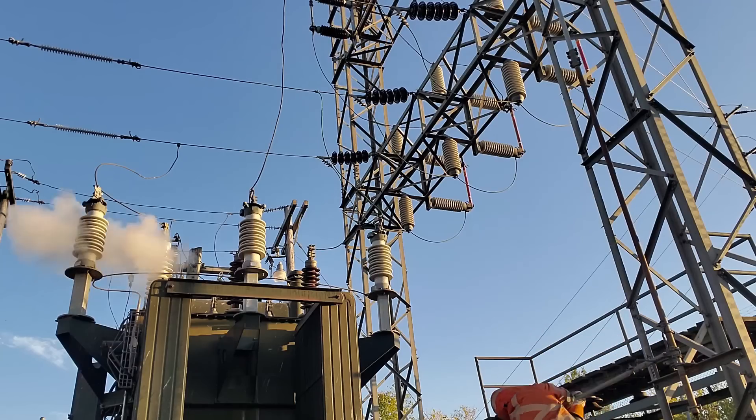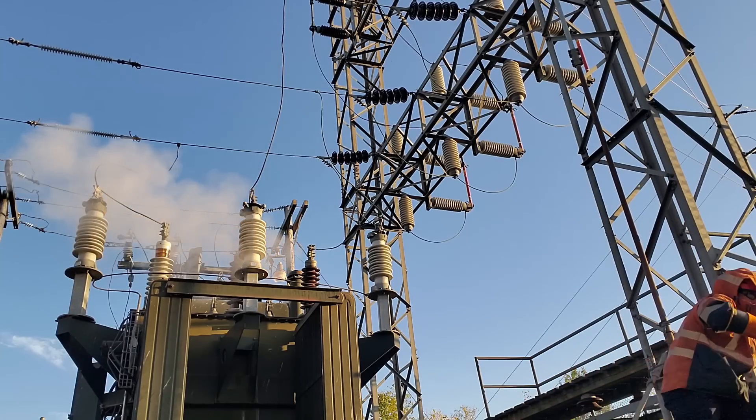You can see in the video where it was — a particular 69kV lightning arrester. The footage was enough to keep the powers that be happy enough to cut it clear, close the power transformer back in, and actually reduce an extremely large outage from what would have been several hours to merely another 20 minutes or so.